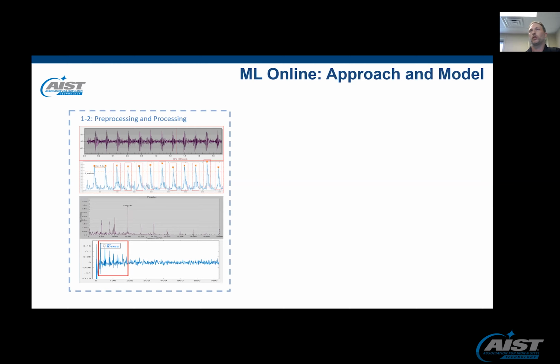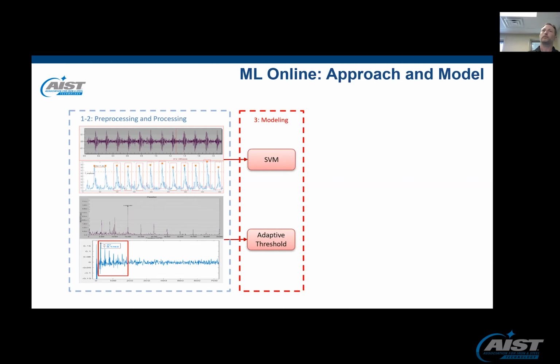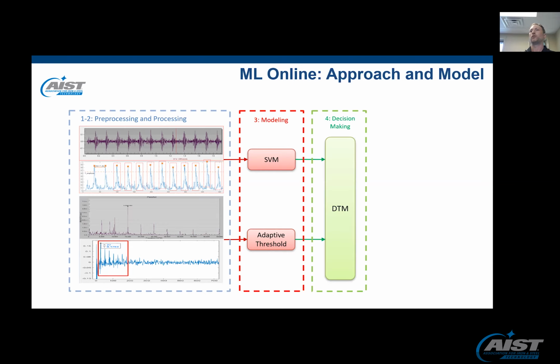The point of the machine learning model is that if we can capture that knowledge and deploy it to the system on site, we've in essence recreated having the expert sit and stare at the data. So our modeling, looking at the impulses, uses a support vector machine, and on the harmonics we use adaptive threshold, feeding into our DTM, which I talked about before - very important. Are the impulses repeating or not in the time waveform? And are the harmonics in the spectrum or not?